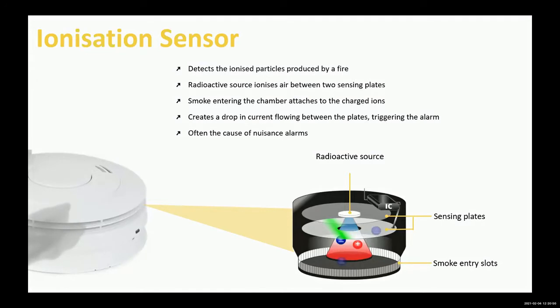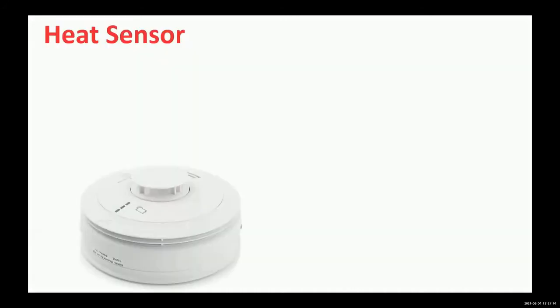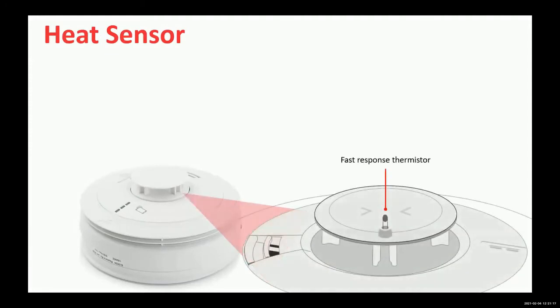Okay. So the radioactive source ionizes the air between the two sensing plates. The smoke entering the chamber attaches to the charged ions. That creates a drop in current between the two sensing plates, which in turn triggers the alarm. So that's it. It's a chemical reaction that takes place within the chamber itself, unlike the optical unit, where it's actually breaking a beam of light. Okay, the heat sensor. The heat sensor has a fast response thermistor under the cover of the unit itself. And in recent years, we have reduced the diameter of that thermistor, which now gives us a faster response to the increase in temperature.